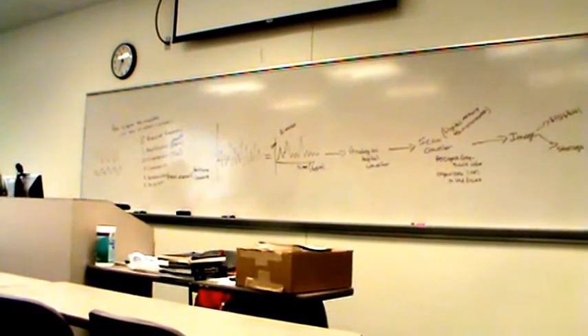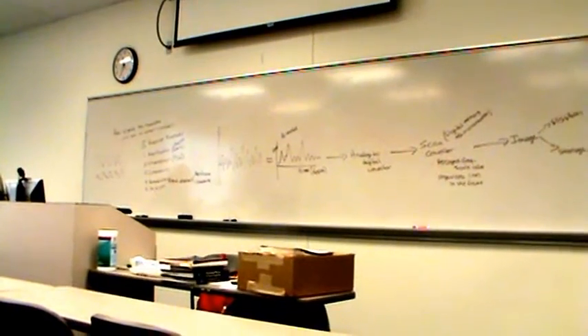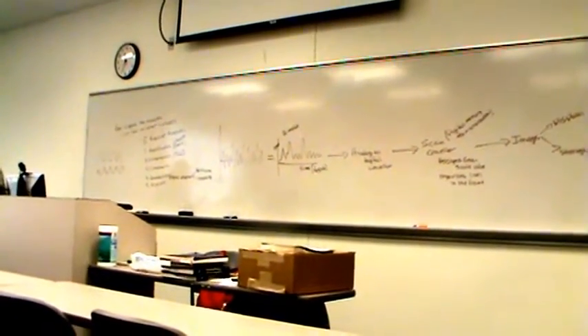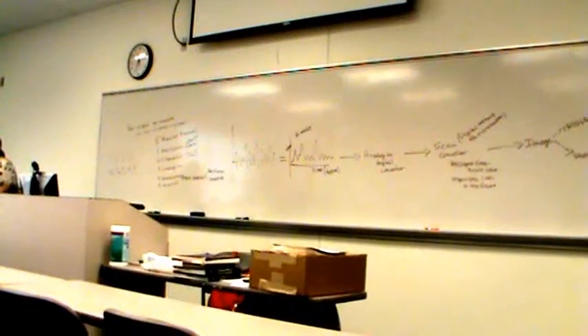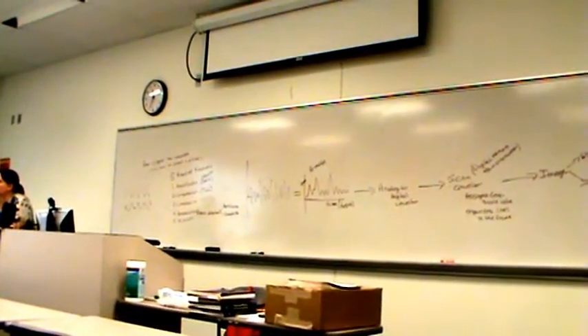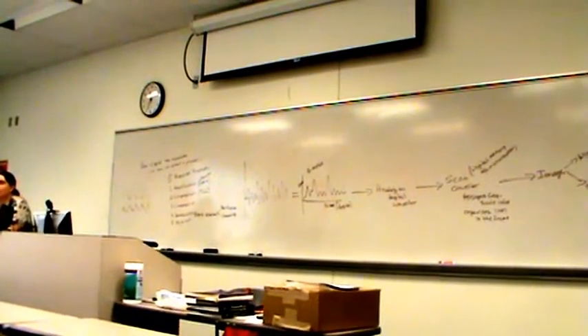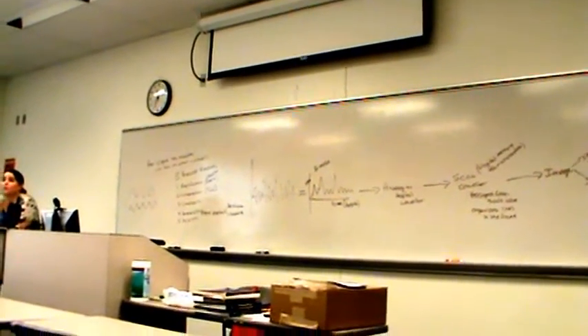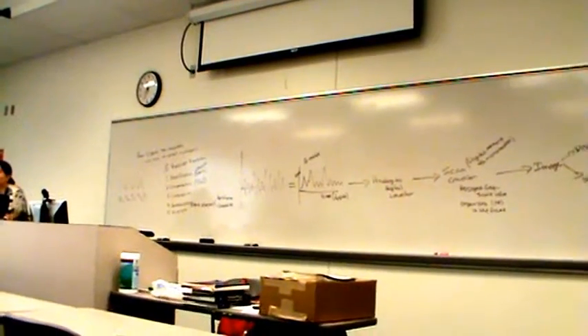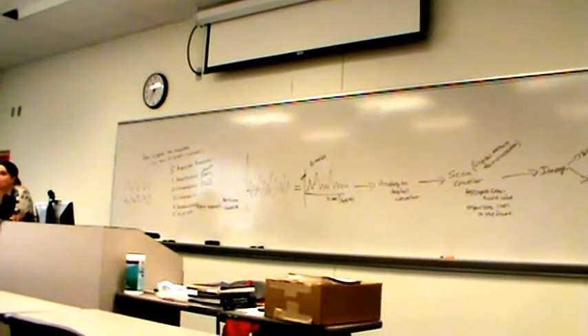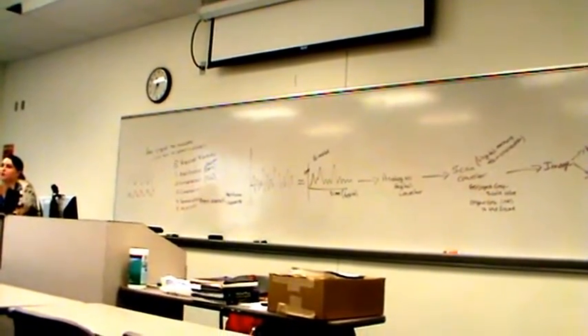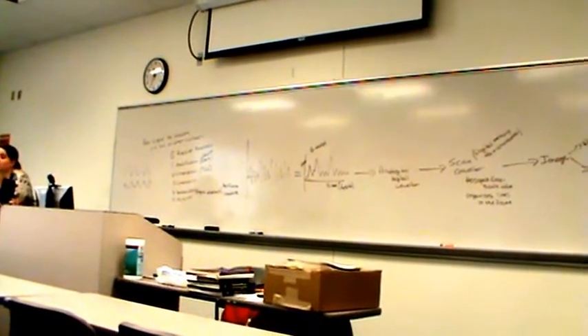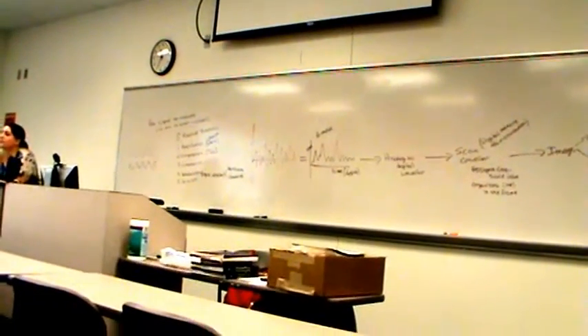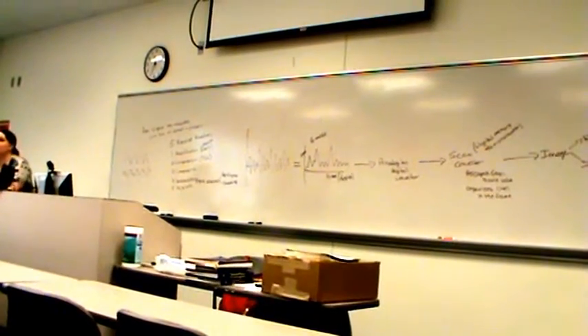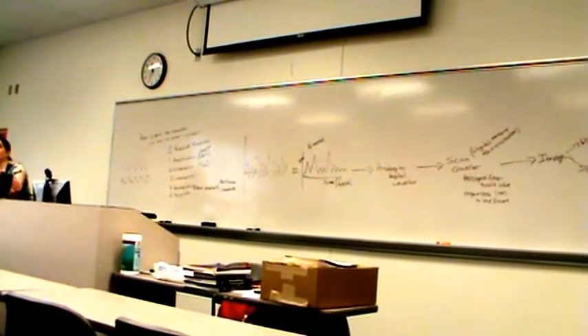Contrast is what you should do first, but typically our response if an image is too dark is to turn the gain up. Then when you take that image back down to our dark ultrasound room, it looks bad because it's overgained. So when you're in ambient light, what you have to adjust is the monitor, not the system. You adjust the brightness and contrast on just the monitor and leave your gain and TGCs and other settings that affect the image that went to storage alone.